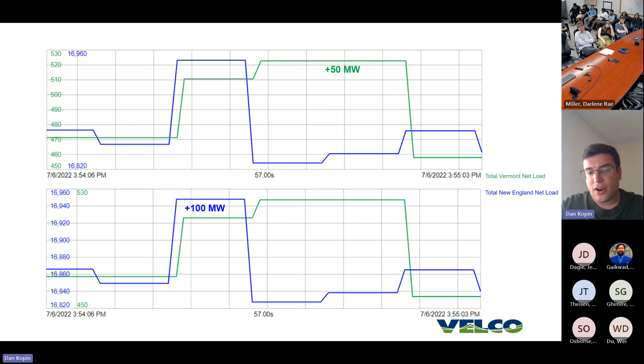But then what ended up happening was that as other generators tripped offline, embedded generation, what they call distributed energy resources, tripped offline in response to rate of change of frequency. And it was 200 megawatts.